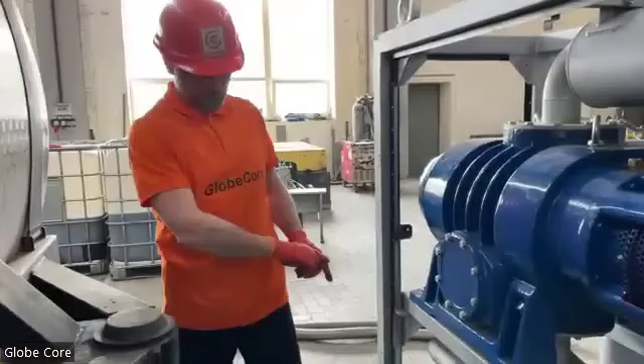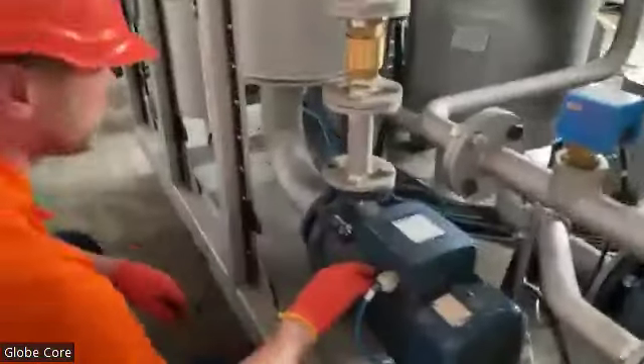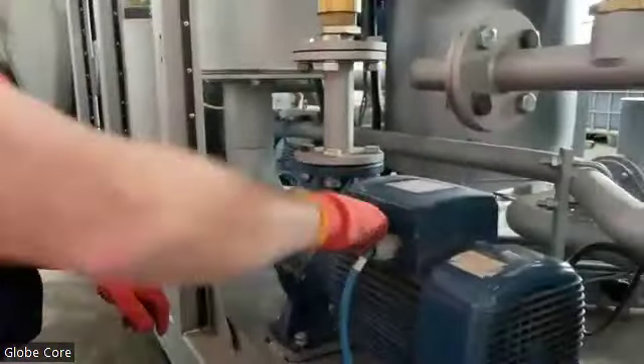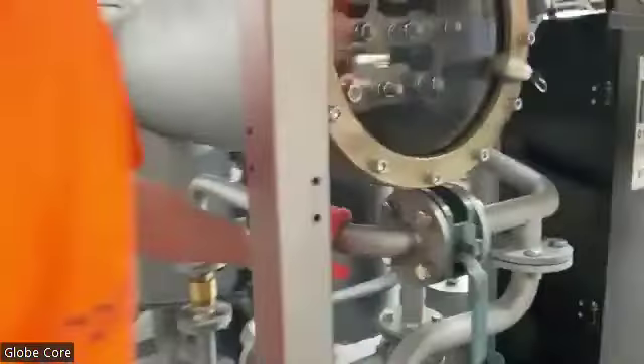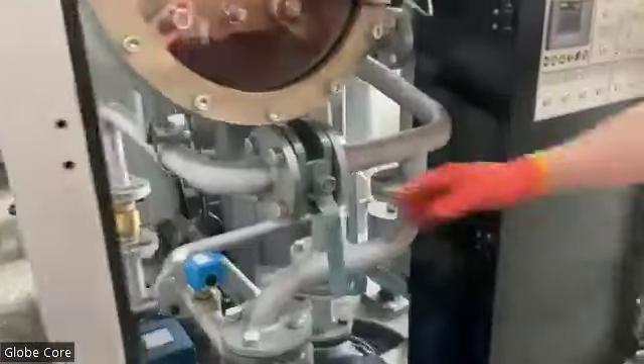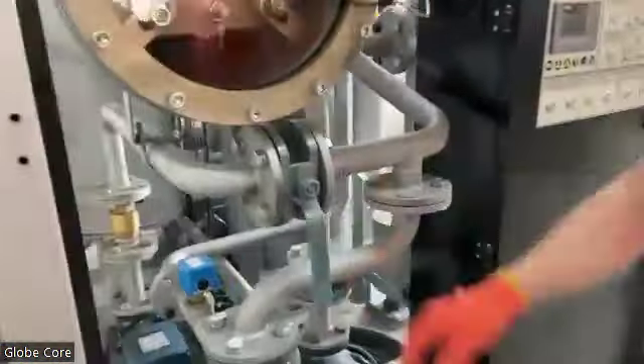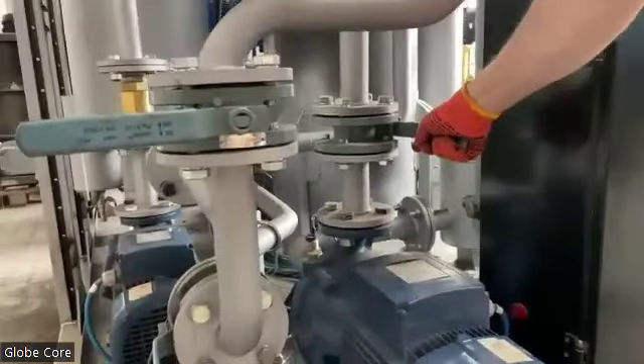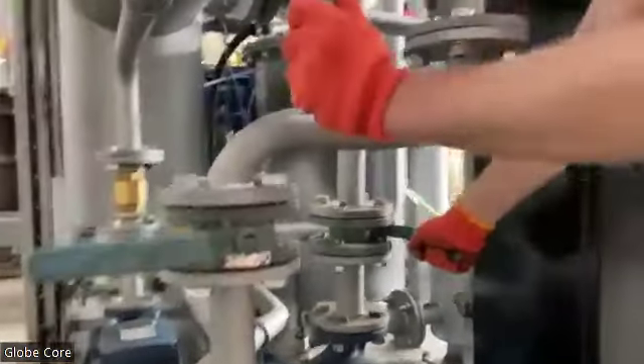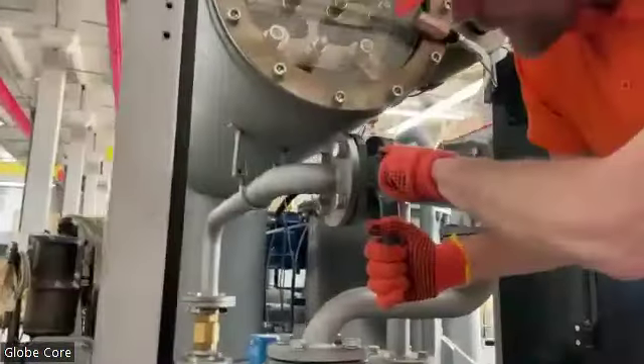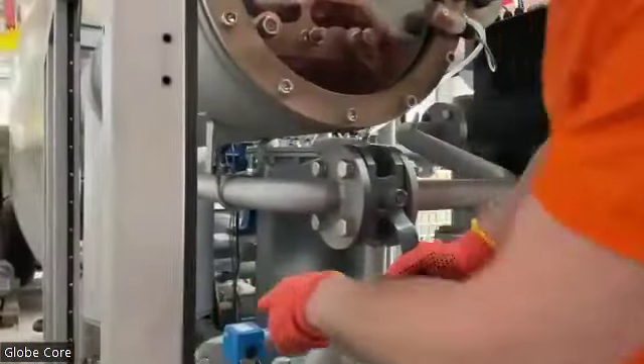So what about the vacuum system? Let's go back to the vacuum chamber and we'll see where the oil goes from it. This is the outlet pump. Again, this is a centrifugal pump. So it takes oil from the vacuum chamber and through the non-return valve, it passes oil to the fine filter through this valve. Do you remember I told you about this one? This valve is used to control the capacity of the inlet pump. And finally, we have this valve to control the capacity of the outlet pump.